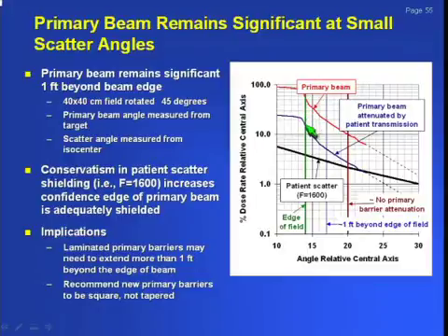As you get to the edge of that beam, that is what's striking your barrier at the edge of that beam. So it is a decrease. Obviously, it is not a full beam, because by definition, where we define the field edge is 50% at the field edge. So when you're looking at your intensity for that last 12 inches of your barrier, it is not a full beam dose rate.